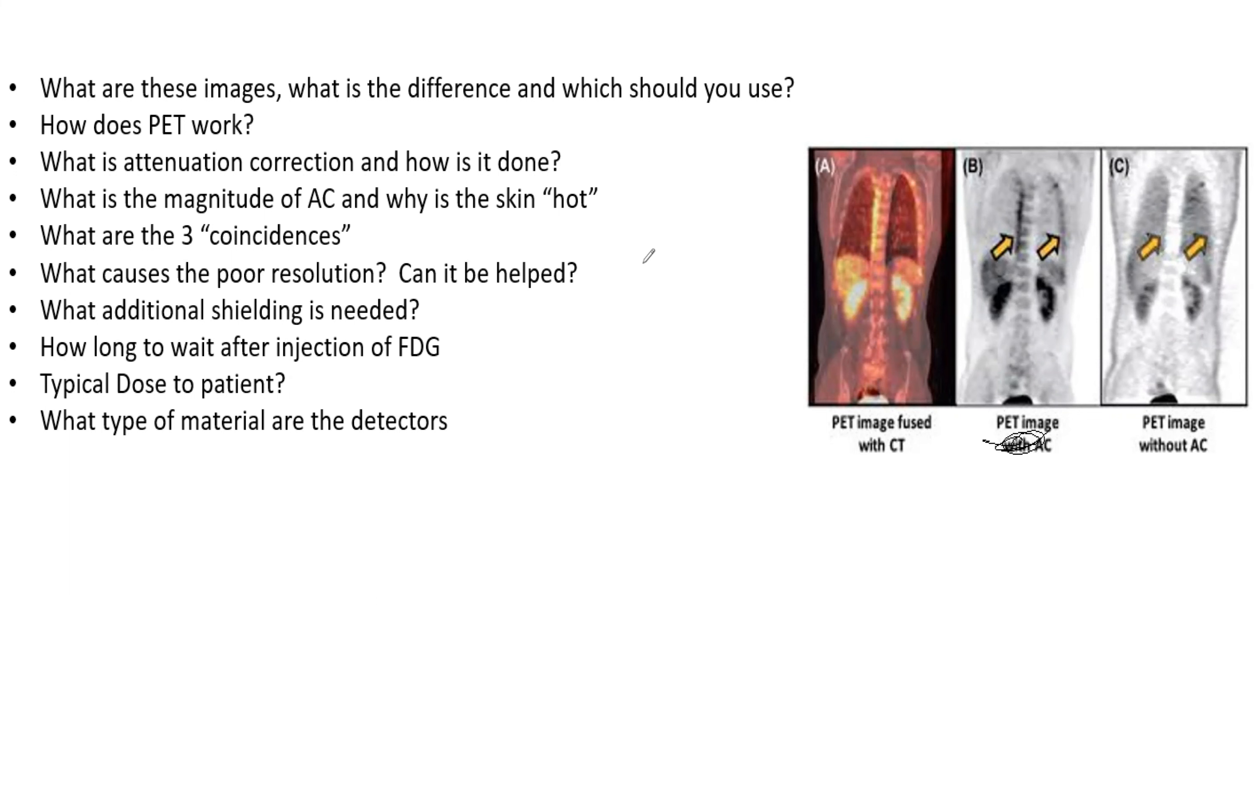So how does PET work? There are detectors that are wired by coincidence circuits. There's an event only if there's a pulse in both detectors within 10 to 20 nanosecond time limits. So we gain projections that make a sinogram, which we can filter back project to get an image. We use FDG, which is a positron emitting tracer in a patient. Those positrons interact with the electrons and make 0.511 MeV photons that are emitted and those are what's detected.